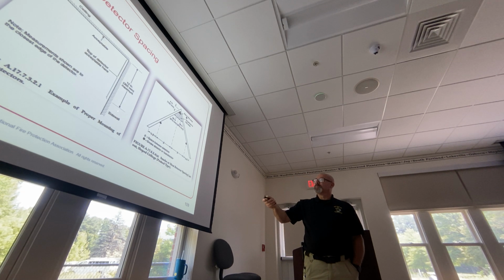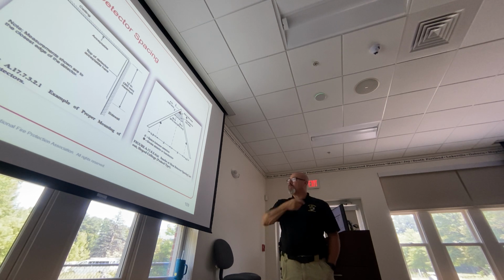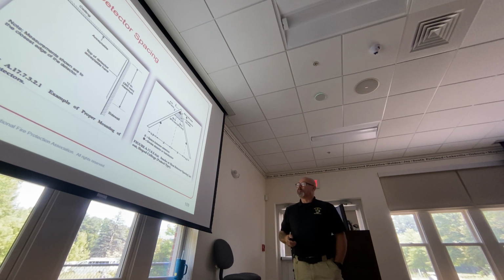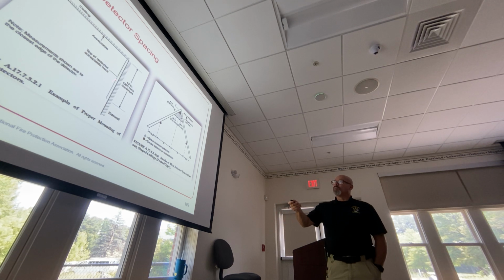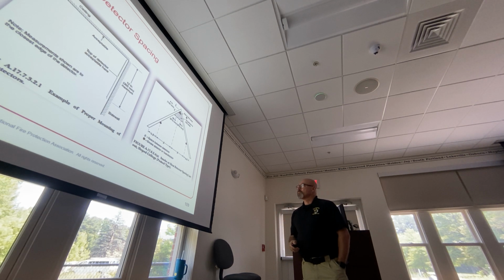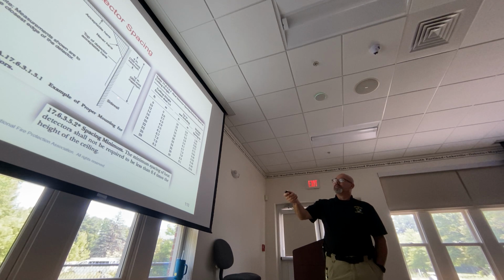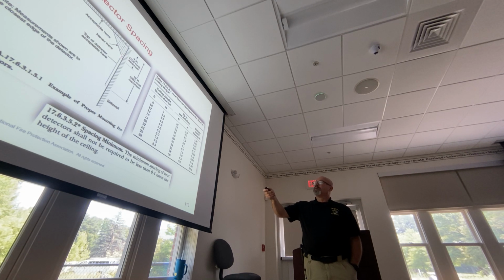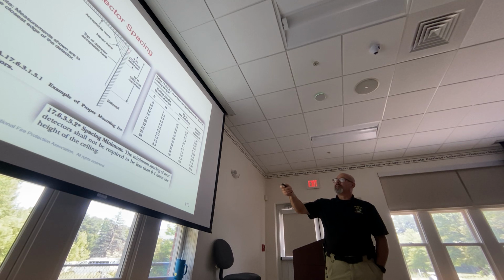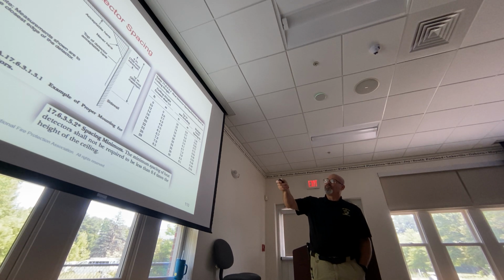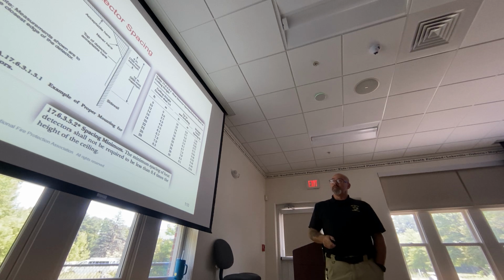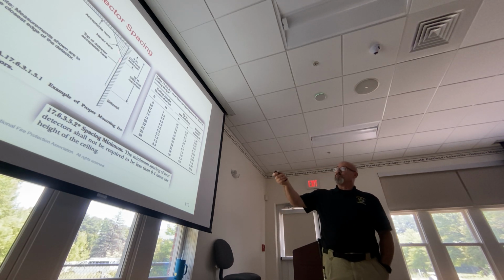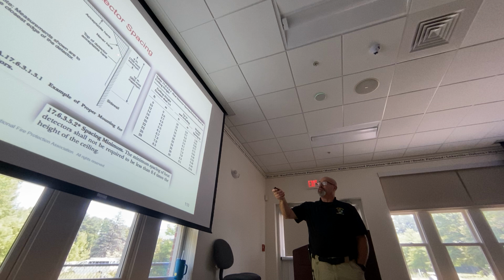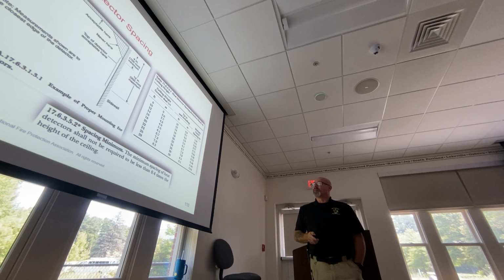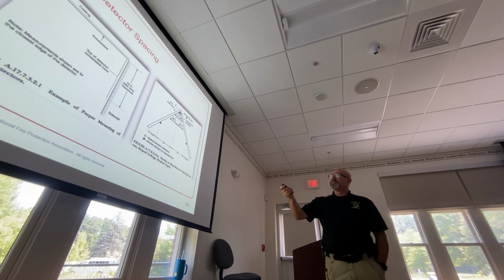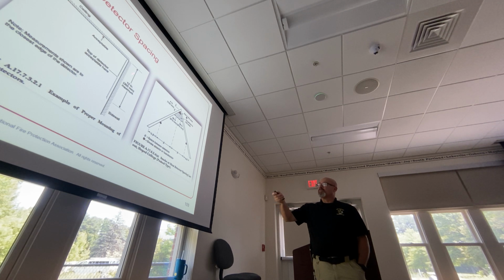Somewhere's maximum of 12 inches down on the sidewall. It's just an example of the proper mounting, on the ceiling, on the wall within 12 inches. The next slide will show you where not to put it, within 4 inches of that triangle, because smoke comes up and it rolls. It doesn't go straight up and then over at a 90-degree angle. Smoke will roll. That's why it's telling you, don't put it within that 4-inch triangle.